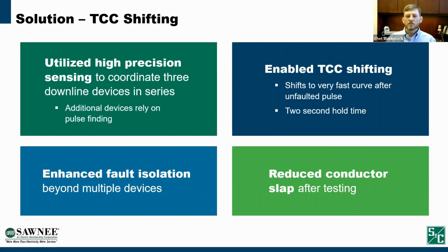So when we started to solve these 2 problems, to overcome these 2 challenges, the first thing that we did is we realized what the high precision sensing for the interrupter really means. And one of the things that it allows you to do is to squeeze those TCCs more close together. So it allowed us to coordinate 3 devices in series where we used to could only coordinate 1.